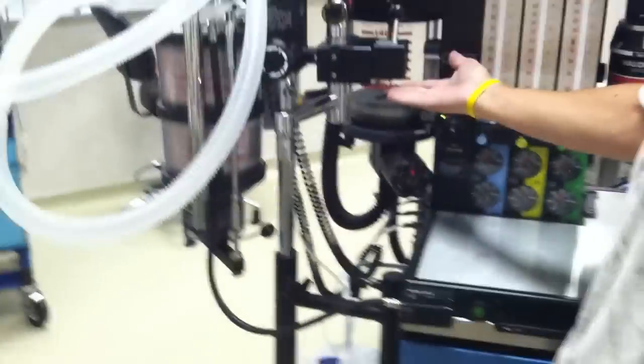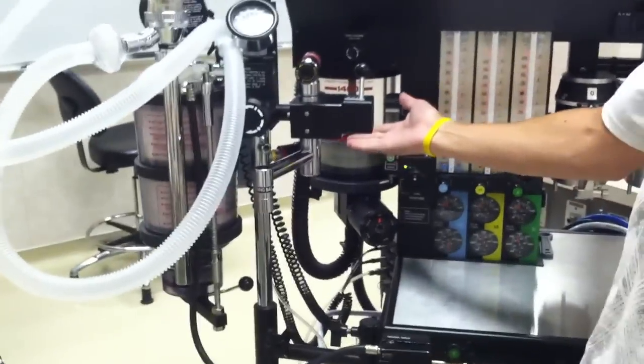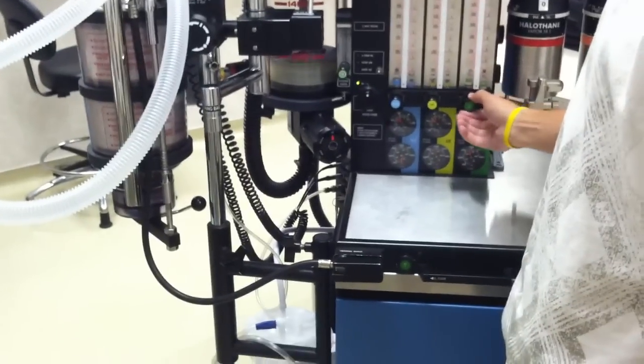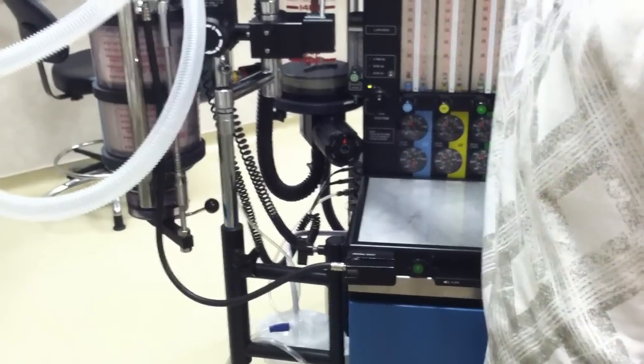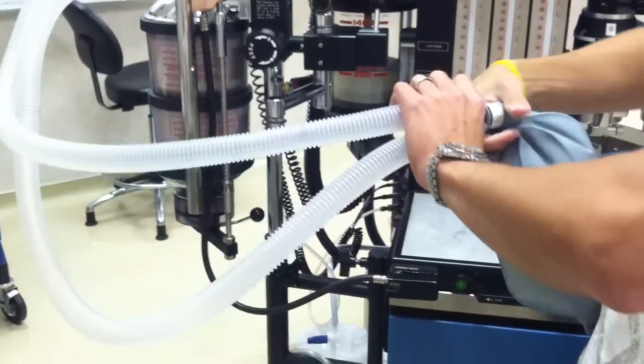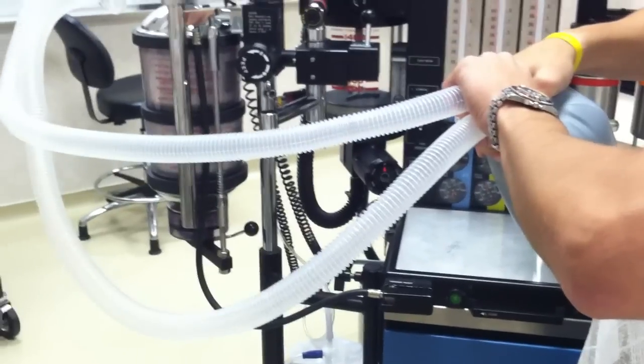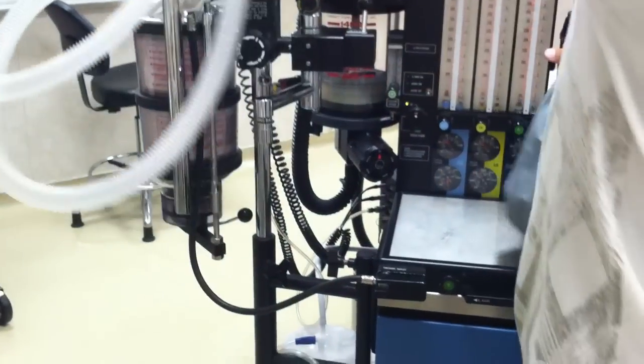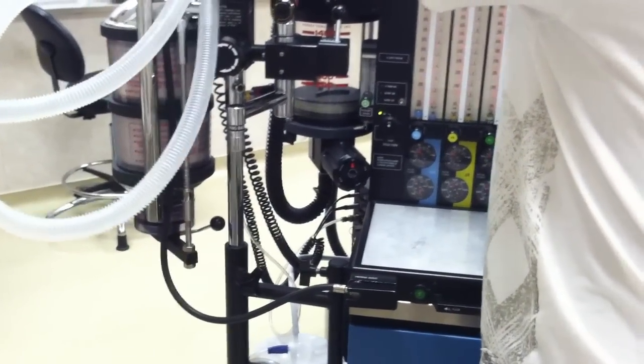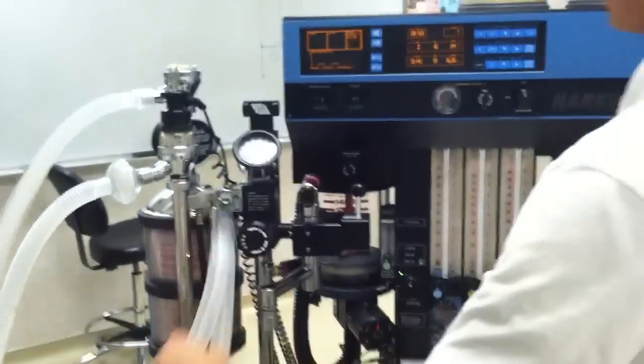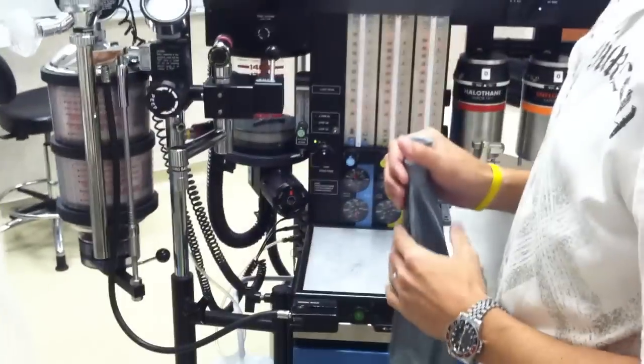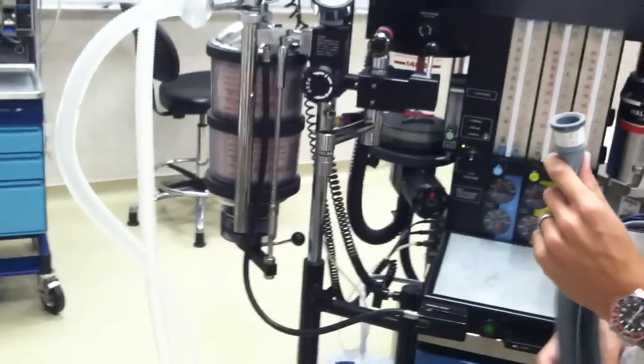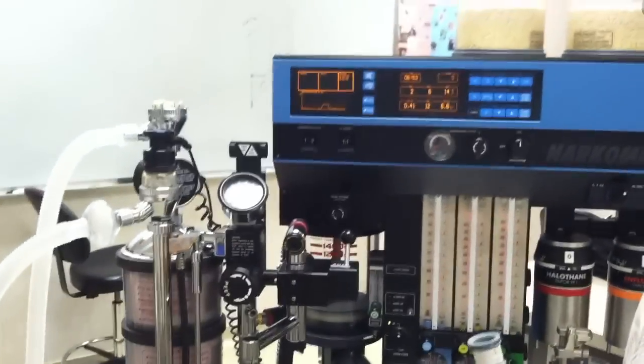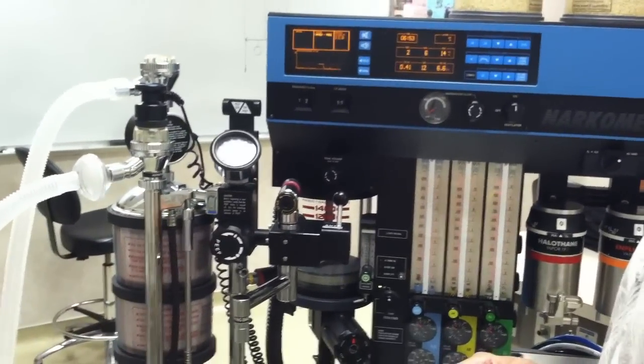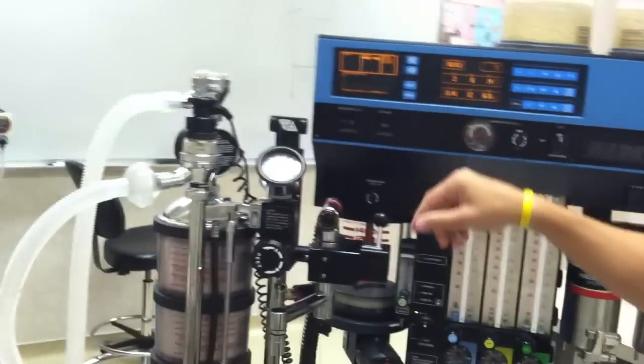You also might have to turn on some flows. I'm making sure that the bellows, there's no leak. It continues to go all the way up to the top. And now I'm going to go ahead and check my disconnect alarm. To do that, you just open this up. You just let that come here. Give it a minute. Should say... And there goes our alarm here, so we know that that's good.